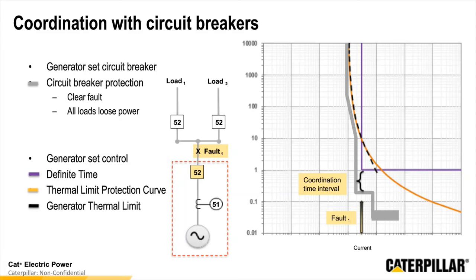And then as we look down more into the short time settings, we now have that difference between the definite time setting of the relay and the short time of the breaker. That's the section where we're going to adjust the time setting, and we'd adjust that time interval to be our coordination overall. If we don't need to provide that, say, 200 or 300%, depending on how that setting is, for more than 0.2 of a second, then we'll set the breaker at that 0.2 of a second and allow the protective relay to be the backup to the breaker. Overall, this is our coordination, making sure that we're aligning these different pieces to allow enough current to support the loads, but that we're protecting against the fault.